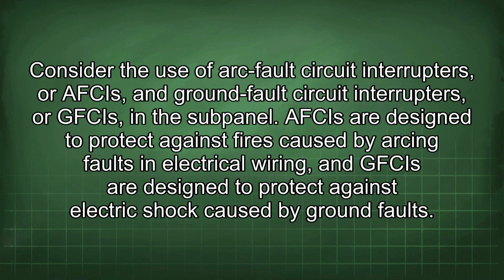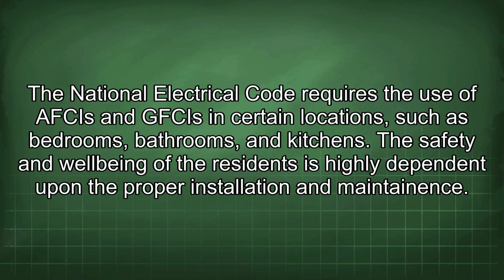Consider the use of arc fault circuit interrupters, or AFCIs, and ground fault circuit interrupters, or GFCIs, in the subpanel. AFCIs are designed to protect against fires caused by arcing faults in electrical wiring, and GFCIs are designed to protect against electric shock caused by ground faults. The National Electrical Code requires the use of AFCIs and GFCIs in certain locations, such as bedrooms, bathrooms, and kitchens. The safety and well-being of the resident is highly dependent upon the proper installation and maintenance.